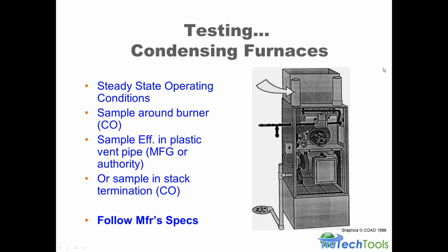Testing a condensing furnace is a little bit different. You again wait for steady state operating conditions, sample around the burner. Sample efficiency in this case would be in the plastic vent pipe, and that would be if the manufacturer or the authority having jurisdiction allows you to do so. And if not, you may have to sample in the termination, which we'll show you a picture of in just a second.